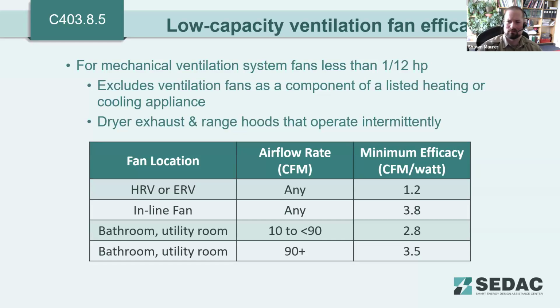There's also some exceptions that were in the 2018 IECC that have been removed in this section. So airflow is required to be tested and verified as well. As we covered yesterday in the residential, you have to test these exhaust fans to make sure they're achieving their labeled CFM airflow rates. Same thing on the commercial side. If we're going to install these systems, you've got to make sure that they're achieving the ventilation rate that they're designed for.